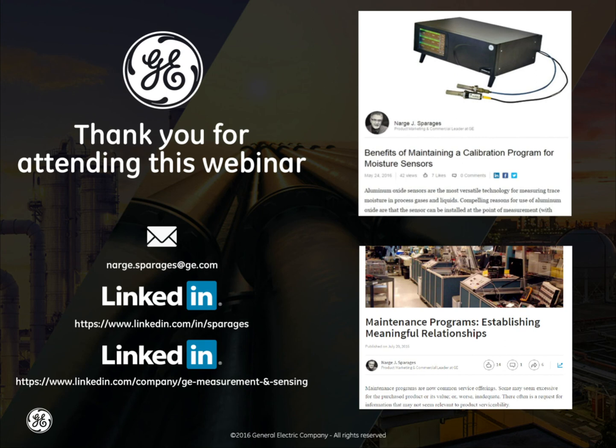Okay, for natural gas applications, the standard in Mexico is 100 ppm. How long will aluminum oxide last before calibration? Well, again, the question is probably best stated as how much do we expect for a change in calibration with time in a natural gas application where the standard is 100 ppm.